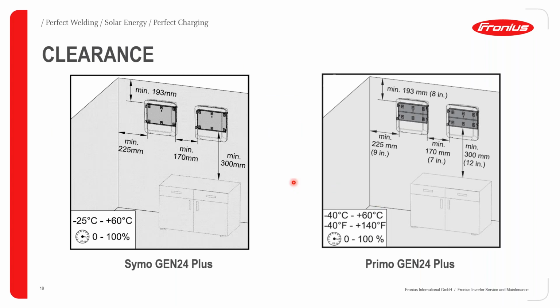In terms of the clearance for both the Symo and the Primo Gen 24 Plus, the clearance upward is 193 millimeters, sorry, and the sideways is 225 millimeters. Side-by-side installation is a minimum of 170 millimeters from the wall mount bracket, and clearance downwards should be a minimum of 300 millimeters from the wall mount bracket, as can be seen described here. The same thing applies with the Primo, as we can see also.